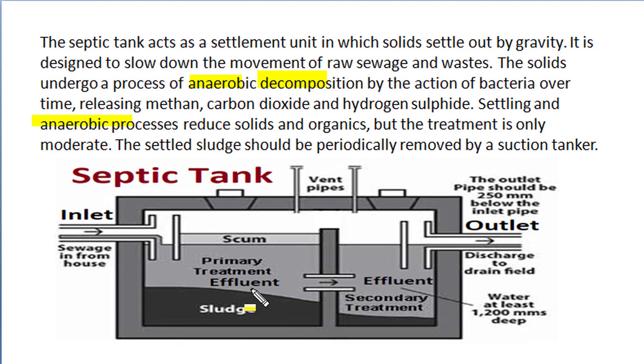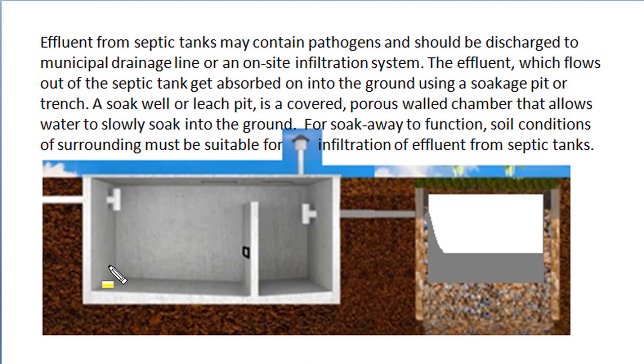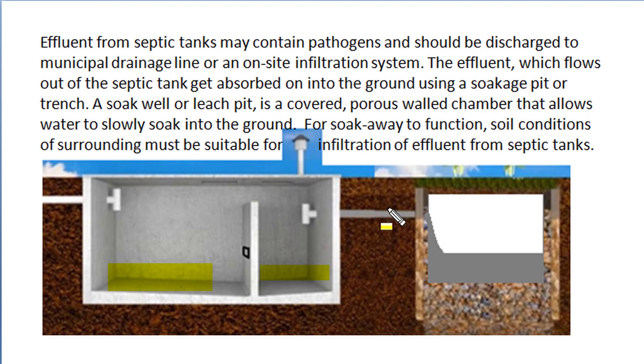Settling and anaerobic processes reduce solid sewage material and other organic compositions, but such treatment of sewage is only moderate, and the settled sludge should be periodically removed by a suction tanker when the septic tank gets filled by sludge formation. Solid sludge of sewage settles in the bottom section of the septic tank, and liquid effluents from the septic tank are allowed to pass into a nearby soak pit. If such liquid effluents from the septic tank are directly discharged in the near vicinity, they may contaminate the surrounding environment as the effluent contains pathogens. This effluent should be discharged to either the municipal drainage line or an on-site infiltration system.